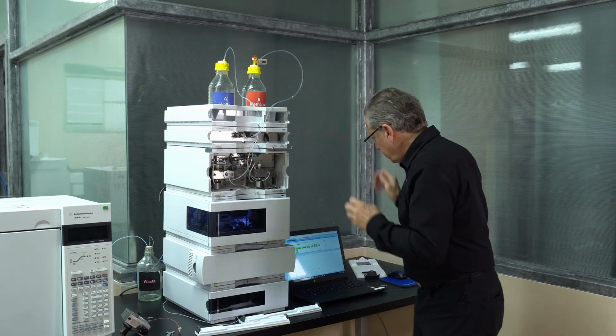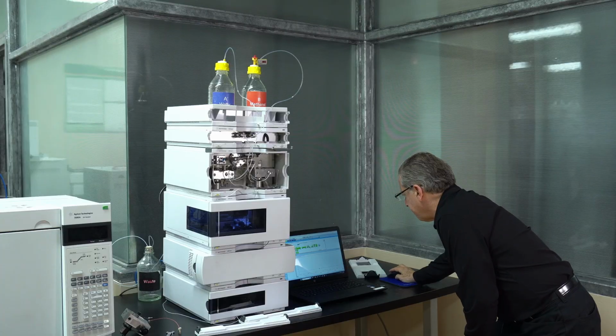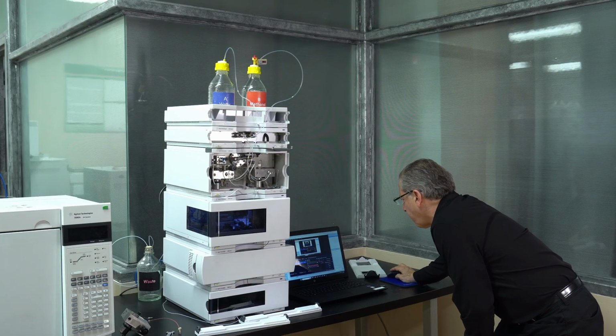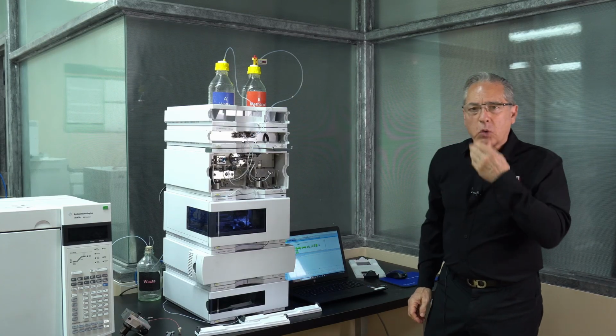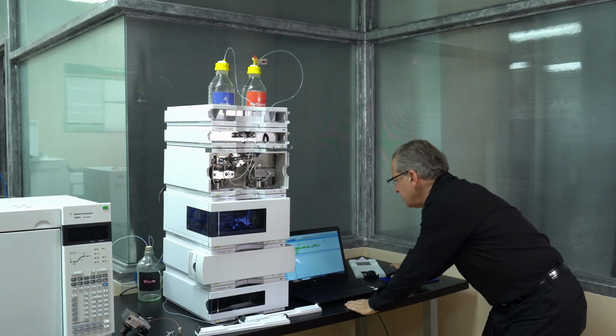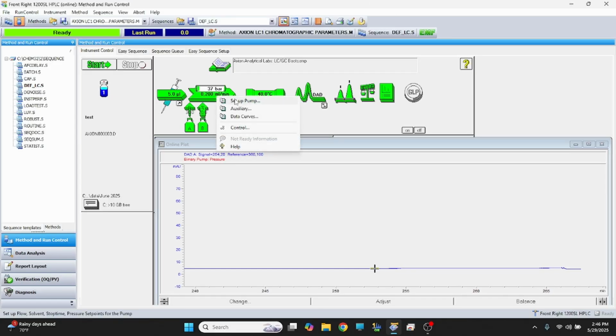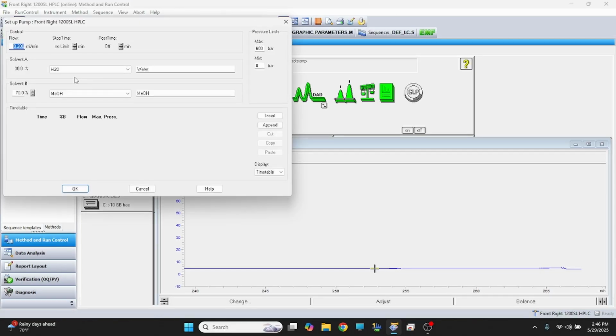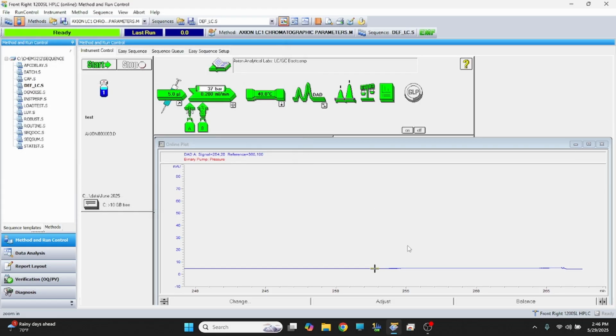As I do this, we're going to go back and forth a little bit, where you're watching both the live LC and what's going on in the software. Right now I've got the flow rate hovering at 0.2 mL a minute. I'm going to take the flow rate to 2 mL a minute, just so we get a reasonable pressure here on the screen. Once it settles out, we'll take a closer look at that.